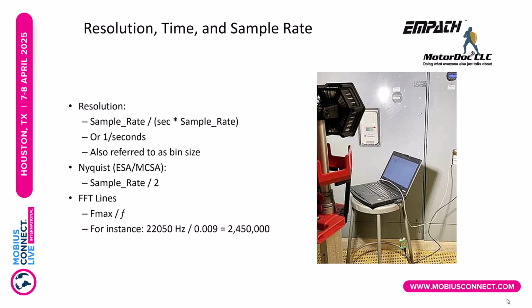So when we do start doing data, just like vibration again, we have to worry about resolution, Nyquist, and the FFT lines. So if I have a sample rate, basically the resolution is 1 over the number of seconds, or basically the bin size. The Nyquist for ESA and current signature analysis is 2. Unlike vibration, where sometimes it'll be anywhere from 2.1 to 2.5, I use 2 because anything that I would see come back from higher frequencies is going to be way over 10 kilohertz.